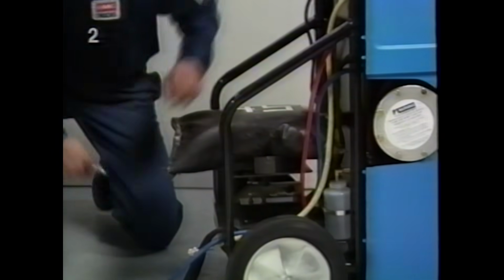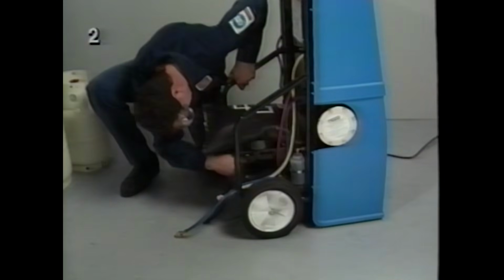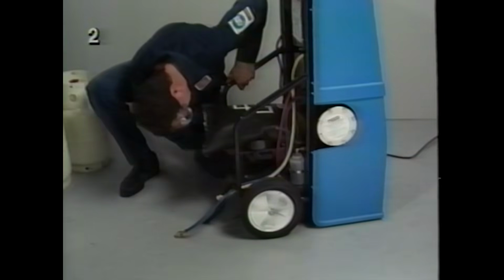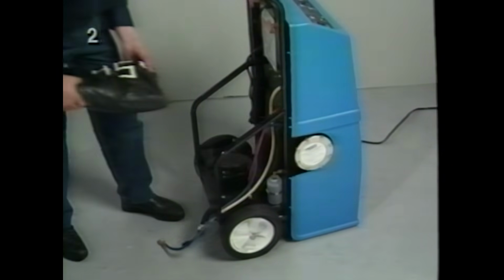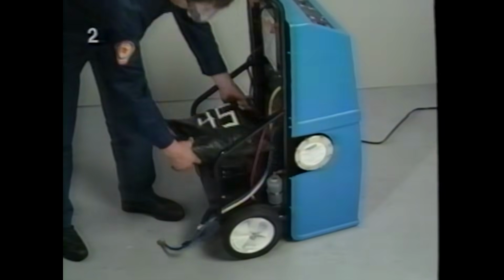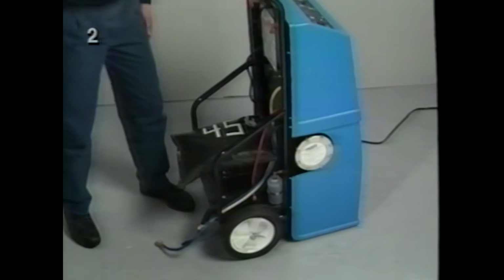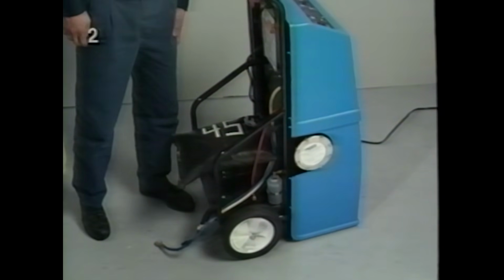If the extra weight doesn't trip the switch, take off the 2-pound weight and undo the lock nut on the trip screw. Turn the trip screw just enough to trip the switch. Tighten the lock nut and take the big weight off too. Check your calibration by putting the 45-pound weight back on. It should trip the switch.